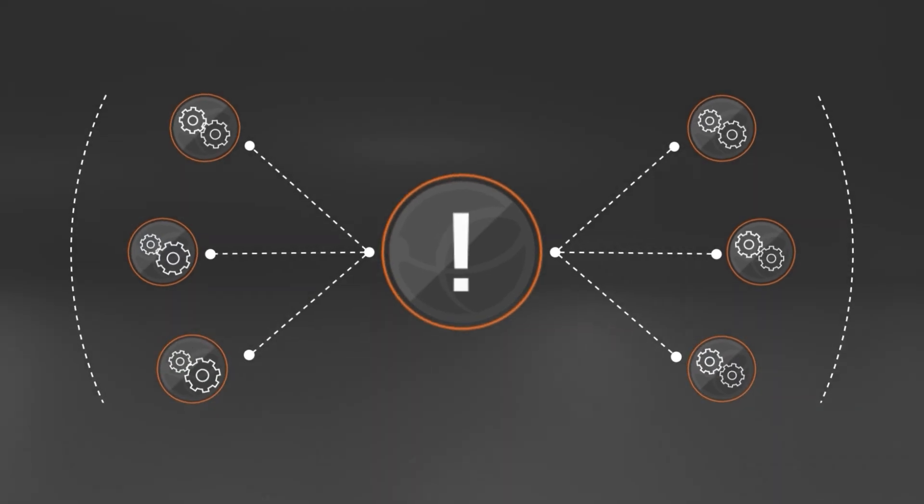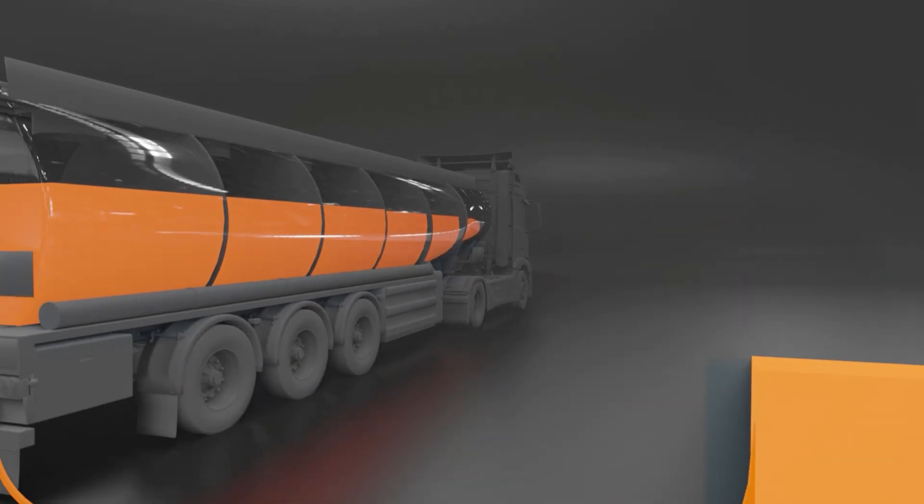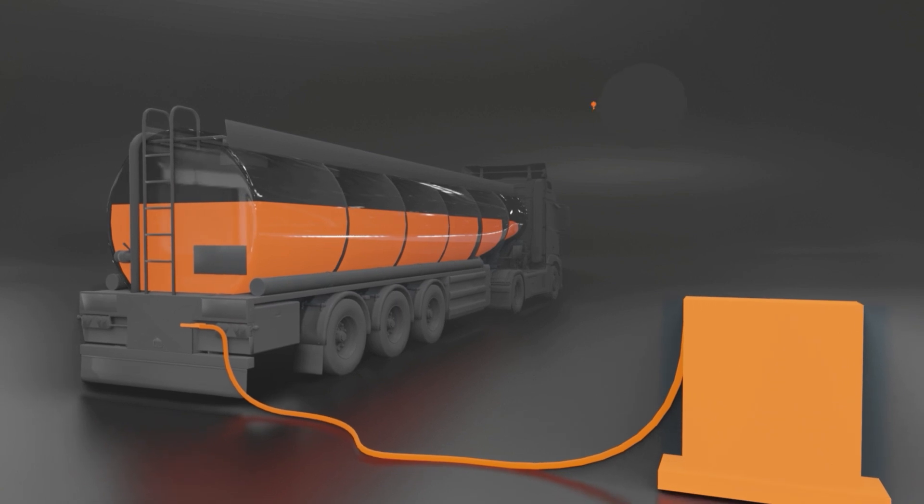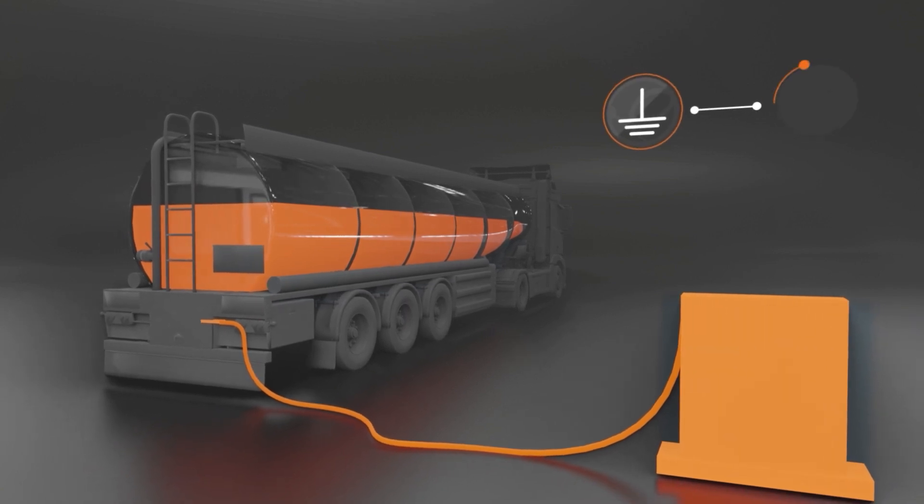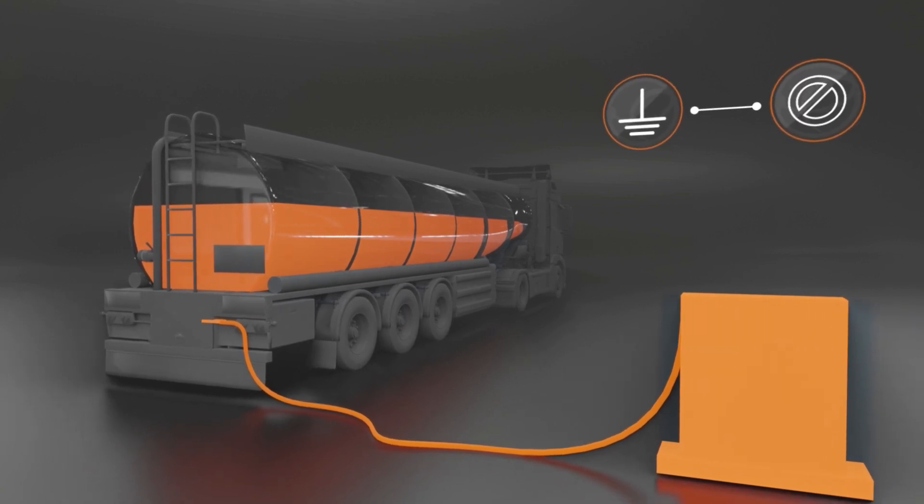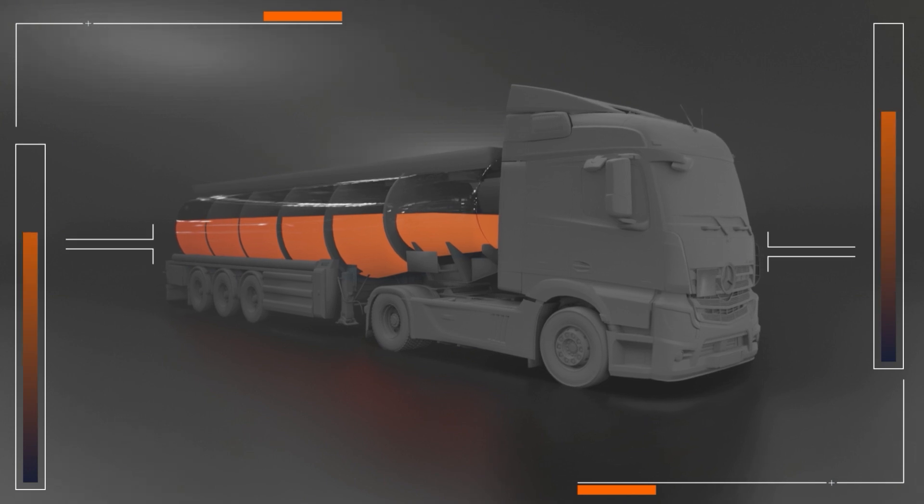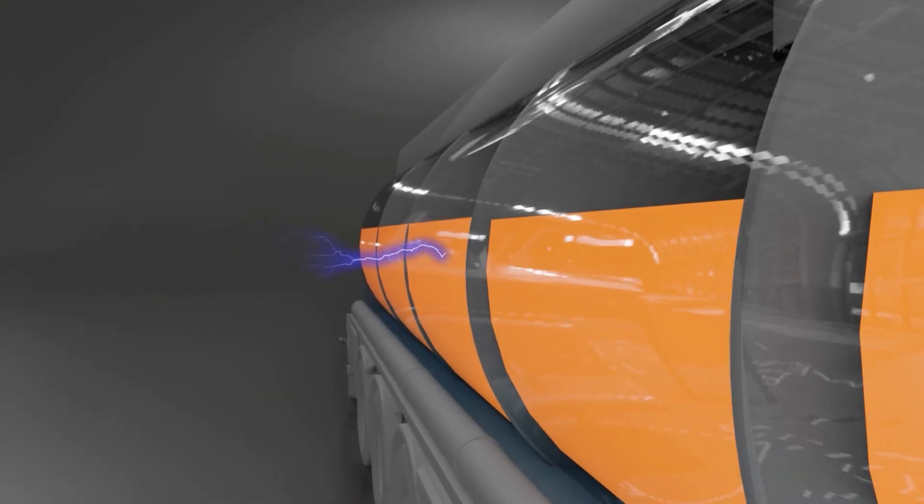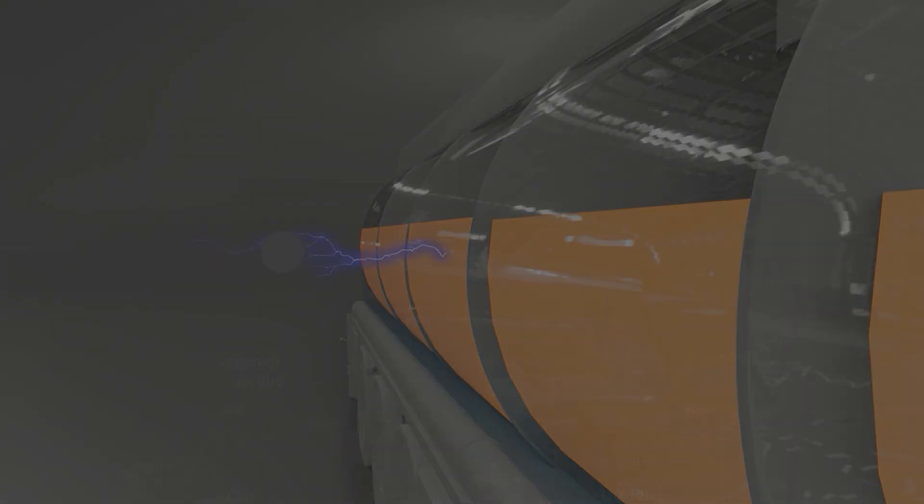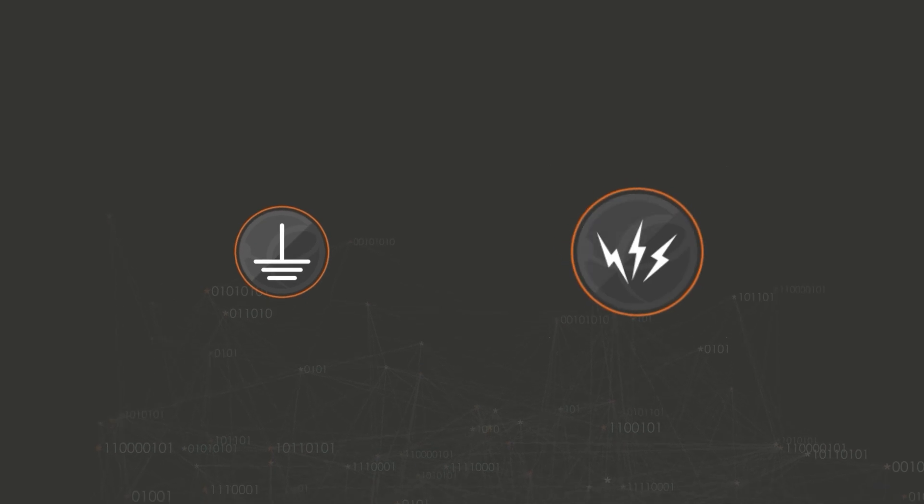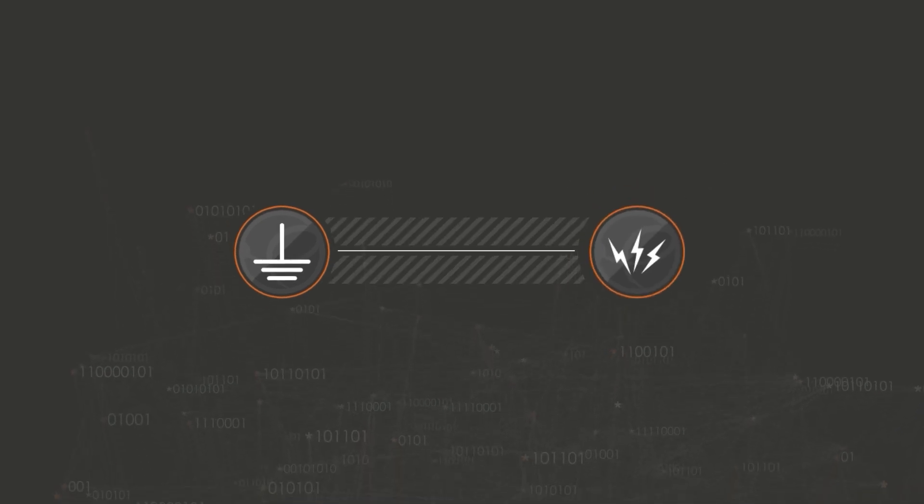There are various ways to mitigate the risk. In an industrial environment, by far the most effective method is through the application of earthing, which will prevent the most common problem: accumulation of charge on a conductor and the release of that energy as a single spark to earth or ground or to another conductor. Earthing reduces the static electricity hazard, but it's important to be aware that it may not eliminate it completely.